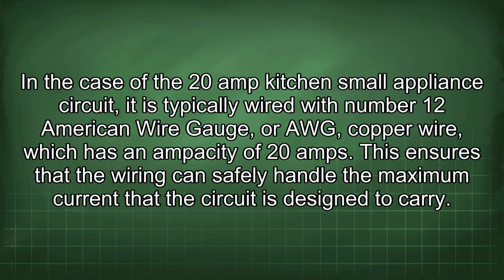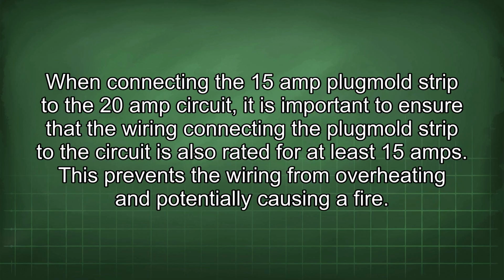In the case of the 20 amp kitchen small appliance circuit, it is typically wired with number 12 American wire gauge, or AWG, copper wire, which has an ampacity of 20 amps. This ensures that the wiring can safely handle the maximum current the circuit is designed to carry. When connecting the 15 amp Plugmold strip to the 20 amp circuit, it is important to ensure that the wiring connecting the Plugmold strip to the circuit is also rated for at least 15 amps. This prevents the wiring from overheating and potentially causing a fire.